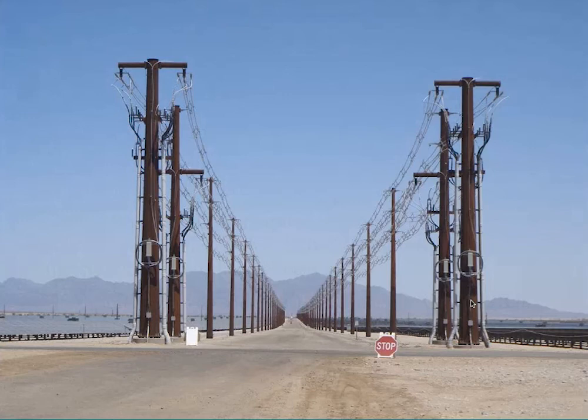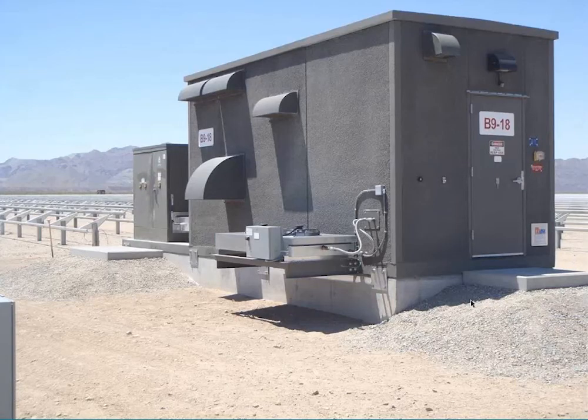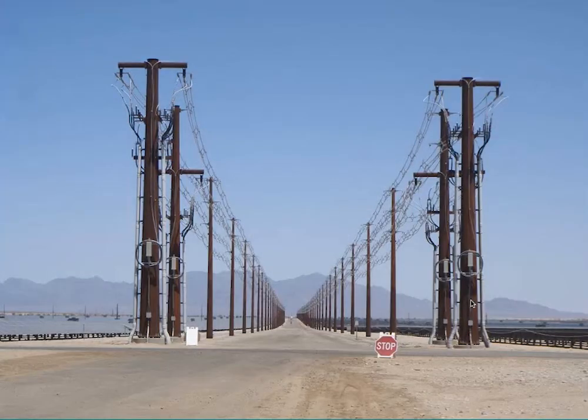Standing right in that location, looking 5 miles in every direction, that's the large-scale PV system. And there's multiple inverters, and from the combiner boxes, they send it into this inverter house that houses the equipment, and it changes it to AC, and it sends it to a transformer on the left side there that you see, a green transformer. And from there, it steps it up to the 35 kV level. We send it down the street to a substation, and then from there, they transform it up to transmission levels. It goes from 35 to, I believe, 230, and then from 230 to 500 kV. Large scale.